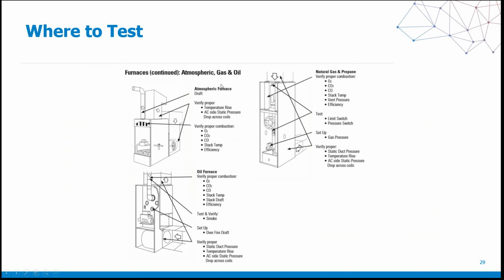And the last slide here, something I really want to touch upon, is your atmospheric system. I talked about atmospheric before, when I talked about the different types of systems and as it pertains to draft. However, as you see here, you have different burners. In a perfect world, I want you to test all these different burners to verify our combustion, to verify our O2, our CO2, and our CO, and our efficiency. And then we want to check in here to verify our draft, our temperature rise, and things of that nature. But again, when we talk about atmospheric, in a perfect world, and not everything is perfect, you can test the different burners here.